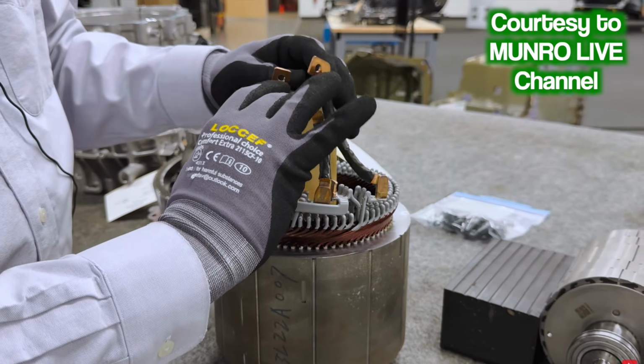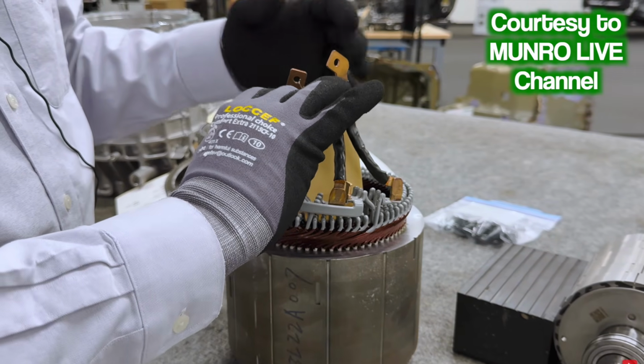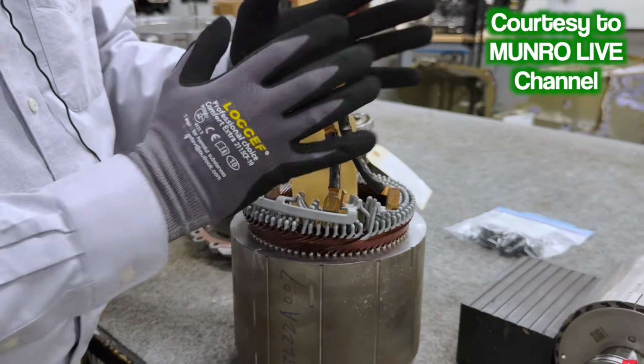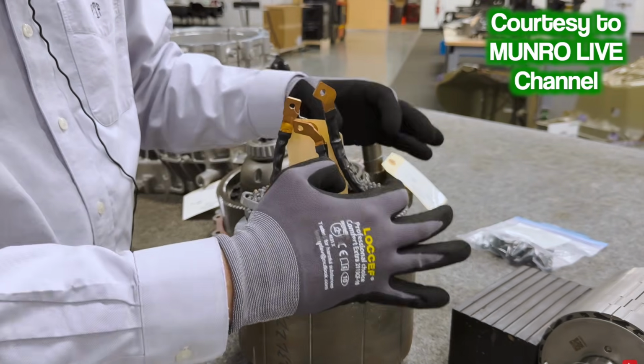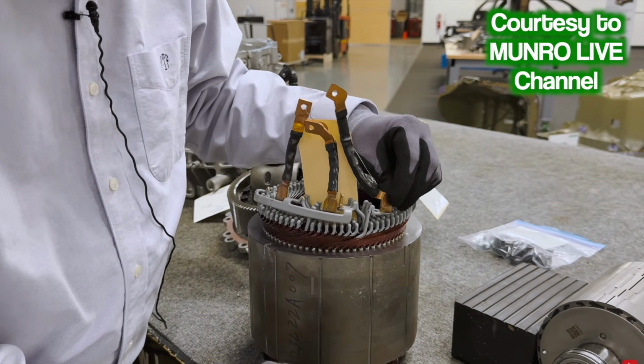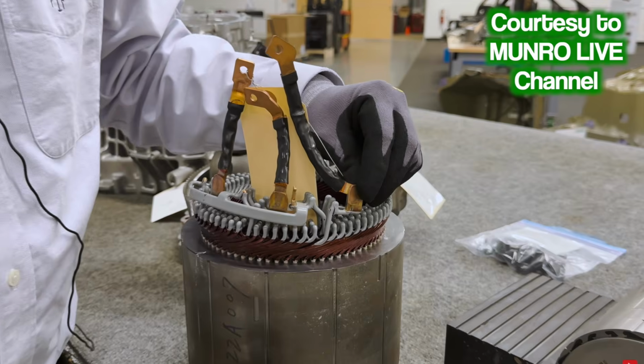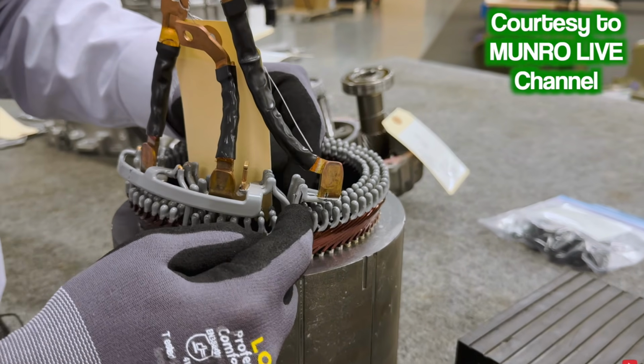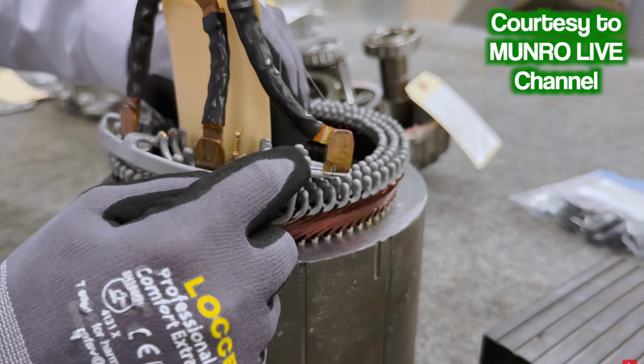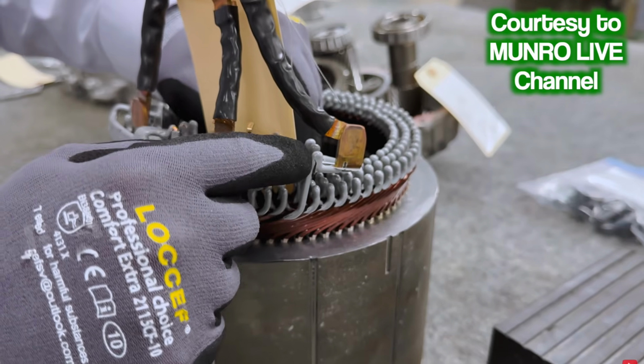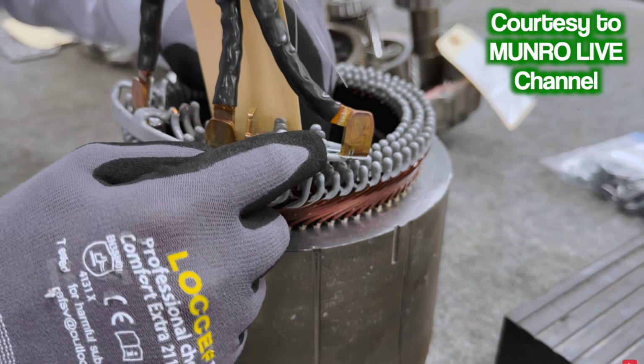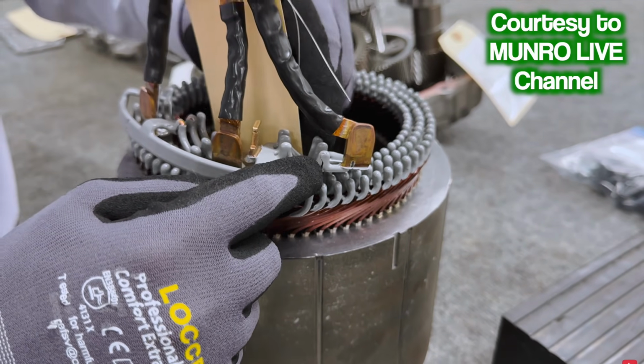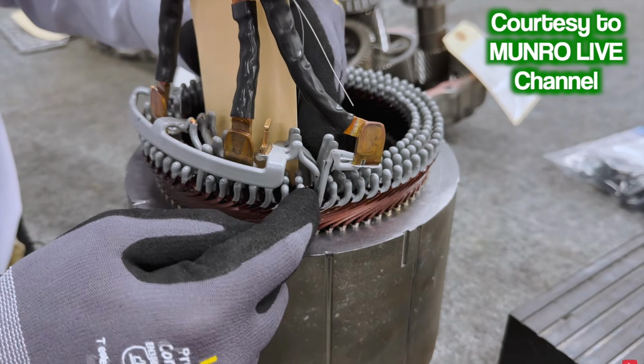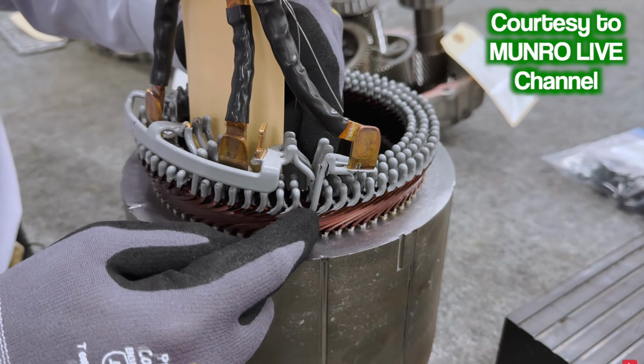This end is supported at the inverter in a plastic block that holds everything tight. But this end is free to move. It's only supported by the wires from the stator, by this weld here, the same weld we're using to conduct electricity into the winding.